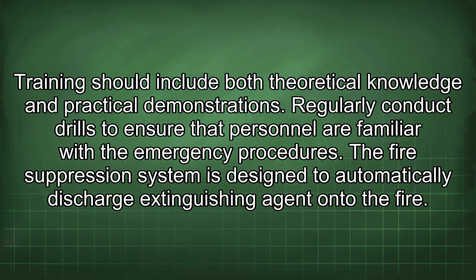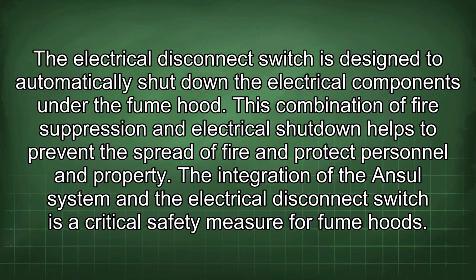The fire suppression system is designed to automatically discharge extinguishing agent onto the fire. The electrical disconnect switch is designed to automatically shut down the electrical components under the fume hood. This combination of fire suppression and electrical shutdown helps to prevent the spread of fire and protect personnel and property. The integration of the Ansul system and the electrical disconnect switch is a critical safety measure for fume hoods.